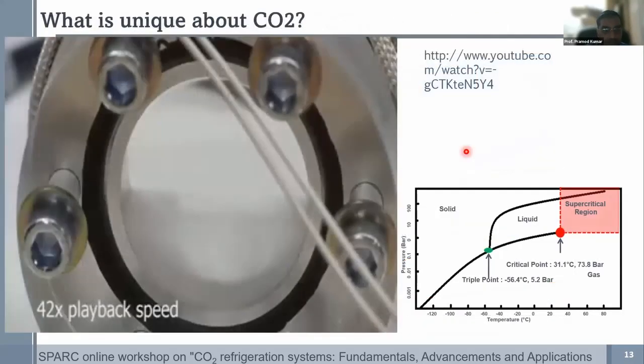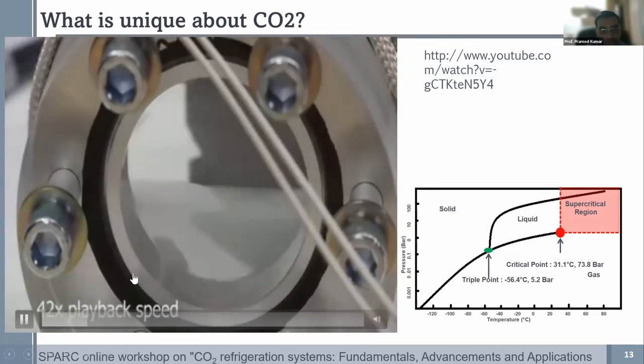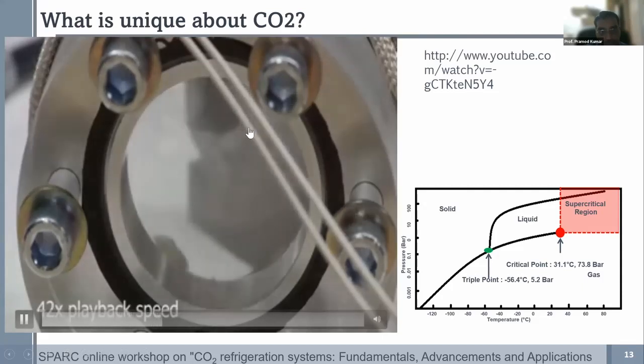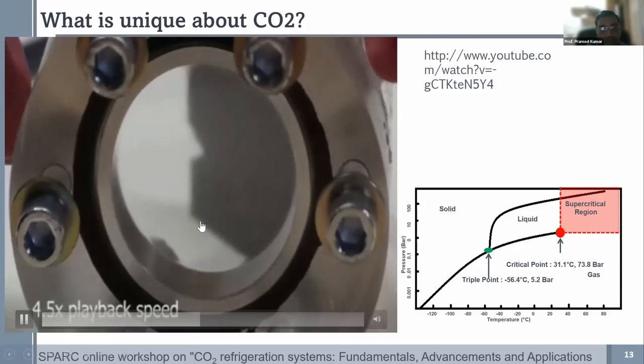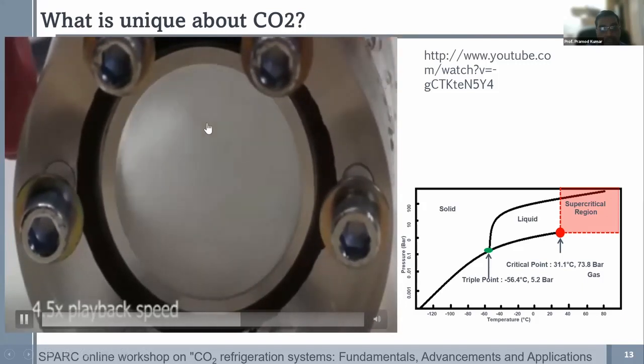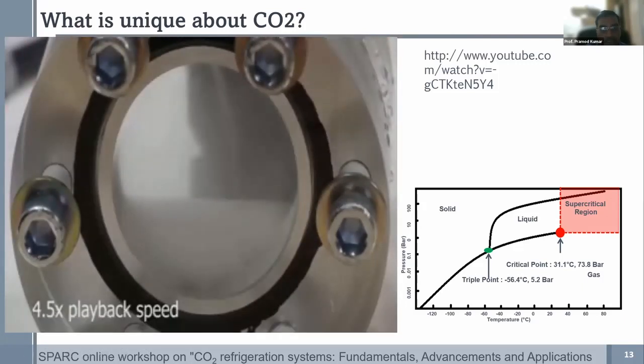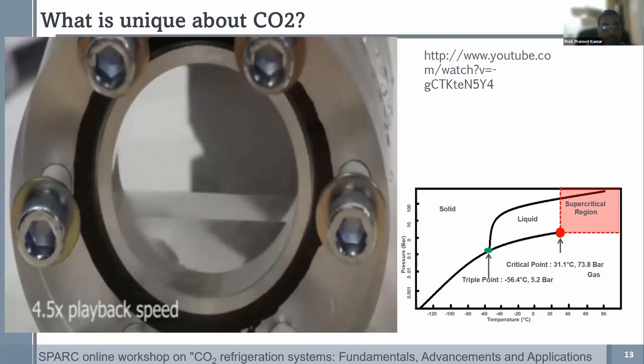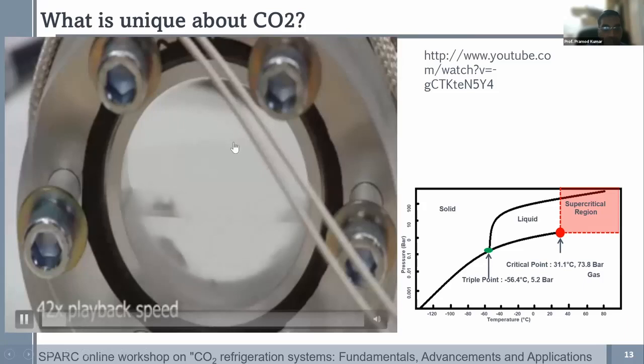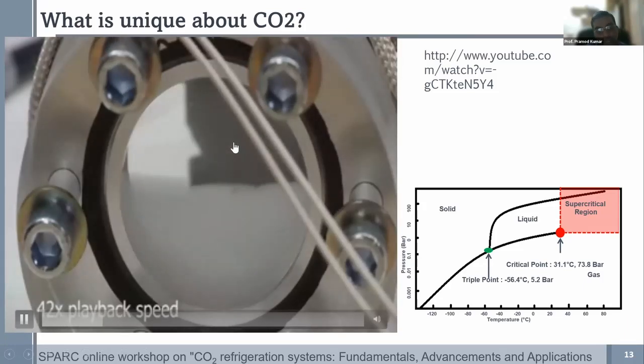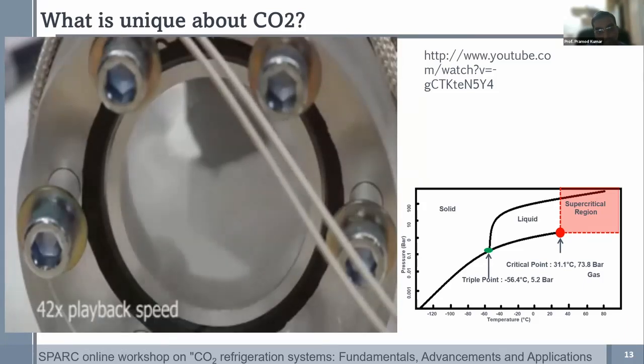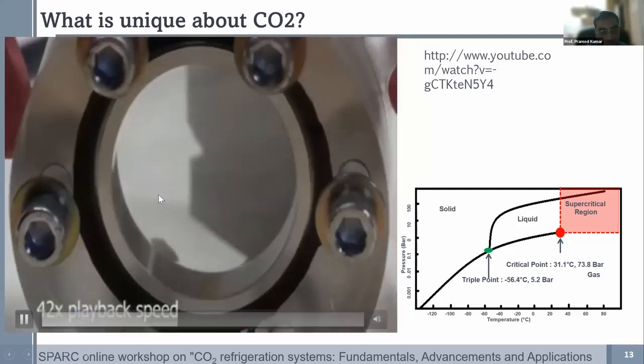Of course, one of the main advantages of carbon dioxide is in the supercritical phase. Once you heat it and the pressure goes to about 74 bar, you can see through a crystal clear sight glass that the carbon dioxide has the density of a liquid, and yet behaves like a gas in terms of occupying the entire volume. So this has tremendous advantages both in terms of power generation and refrigeration.